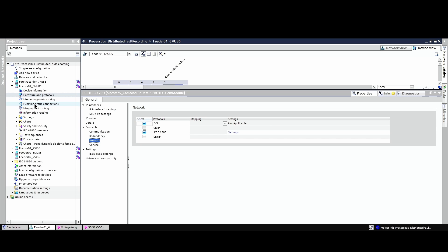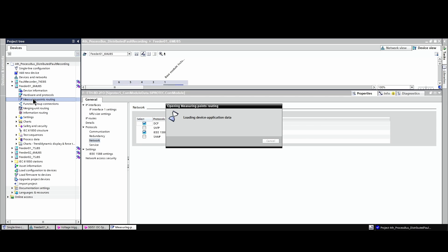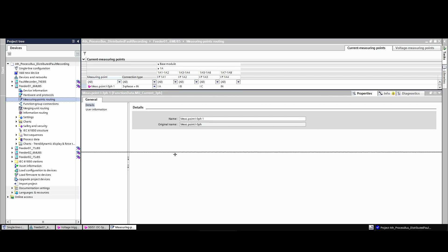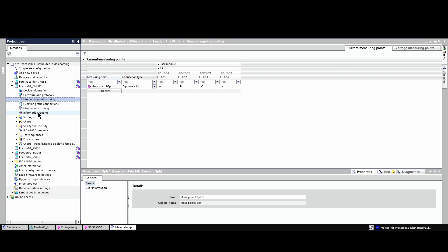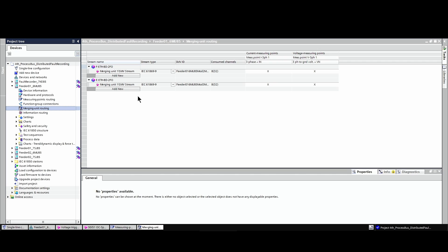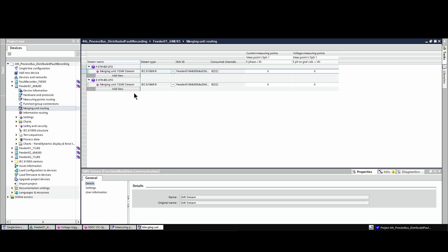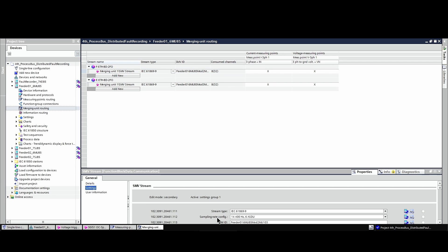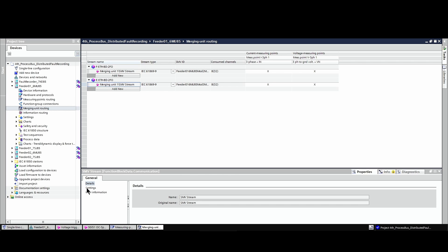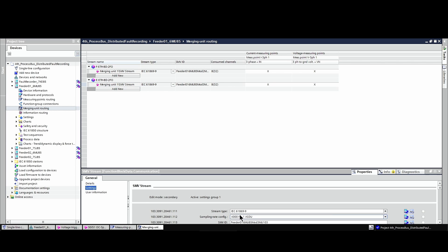Now we take a look at the measuring point routing of the merging unit. We can see that the merging unit is connected to the physical voltage and current transformers on the rear side of the device. In the measuring point routing we can see the two streams. Communication module on port F shows a 14.4 kHz sampling rate, which will be connected to the 7KE85 fault recorder. And on communication port E we have a second stream providing a 4 kHz signal, which provides measured data to the 7SJ85 protection relay.